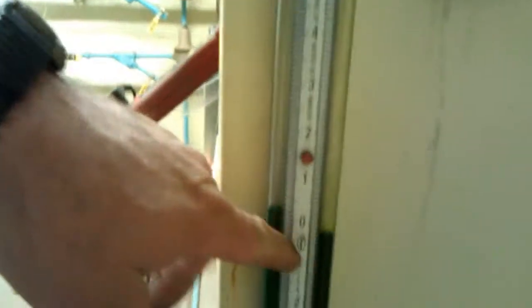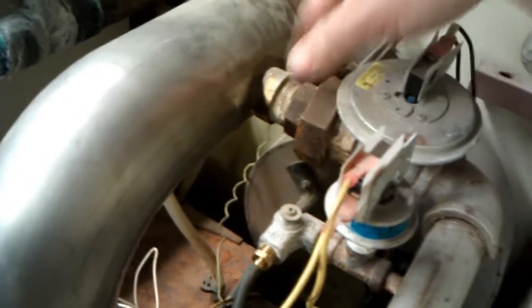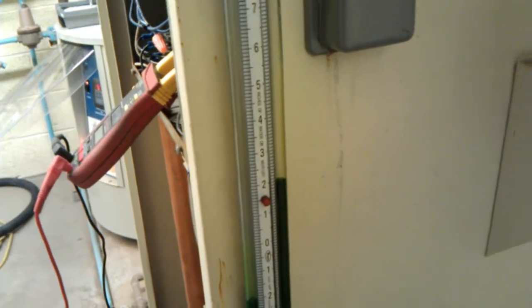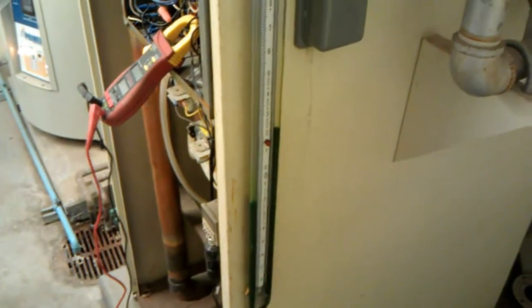Got ignited current. Initial negative pressure from the venturi effect of the blower pushing air through the reducer and by the port here. Got a slight low pressure measured right here. There we go. Now it's positive. So we're about 1.7 to 1.8, so we're about 3.5 to 3.6 or so. It's fluctuating a little bit, but that regulator's backed out all the way it could go to still get the cap on. So I guess that's what's going to run.